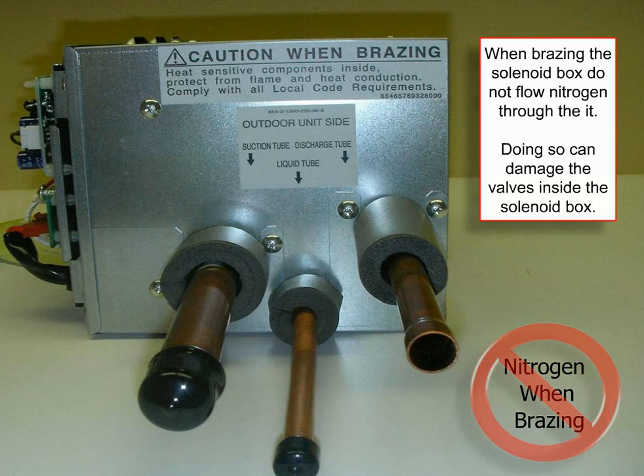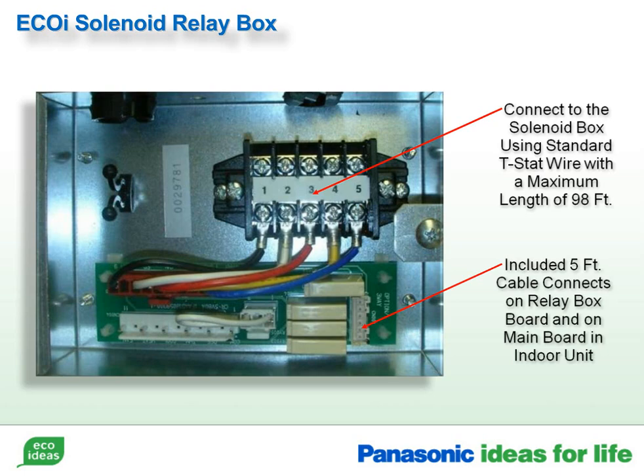It is also recommended that the solenoid valve boxes be installed in a hallway and not in a noise-critical area, so that the solenoid's clicking noises cannot be heard. The solenoid box can be mounted up to 98 feet from the air handler. The supplied gray cable is 5 feet long. This cable connects the relay box to the air handler. This is the reason that the relay box must be mounted within 5 feet of the air handler.